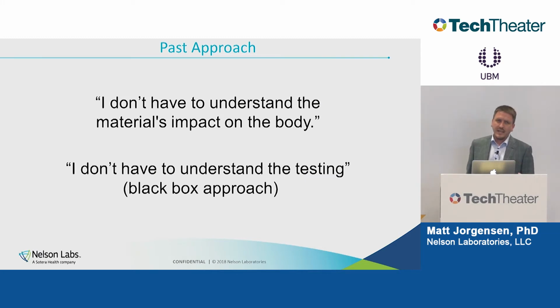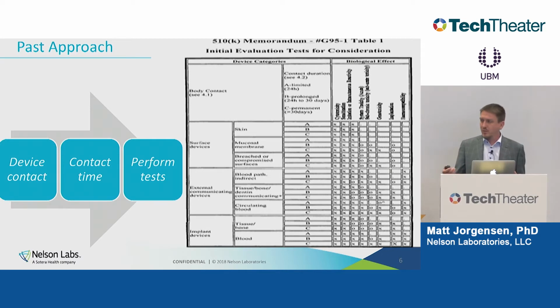In the past, one key limitation was that it was much more of a checkbox approach. As a manufacturer, you'd make a device, categorize it according to its patient contact and the duration of contact, and then in the old G95 you would just go down and checkbox all the tests you'd have to do. While you might think you understand the materials in your device, you didn't really have to understand them to get the job done, so long as you passed all those tests. You didn't have to understand the testing or your materials, so long as it functioned and passed. You would categorize it, look at the chart from the old G95, go across the row, and make sure you passed all of those. It was really a checkbox approach.